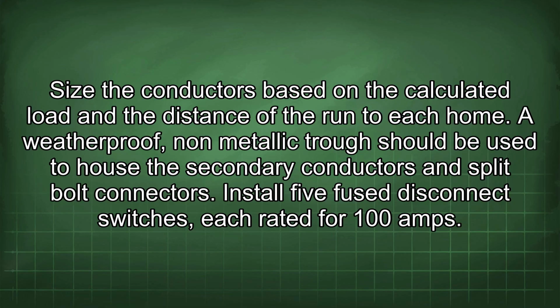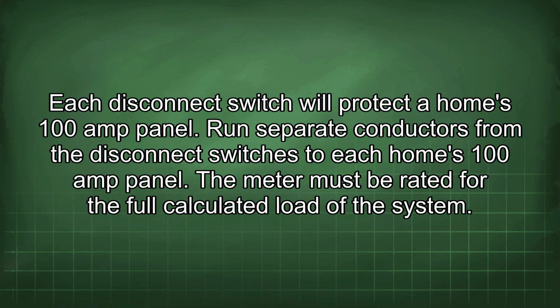Install 5 fuse disconnect switches, each rated for 100 amps. Each disconnect switch will protect a home's 100 amp panel. Run separate conductors from the disconnect switches to each home's 100 amp panel. The meter must be rated for the full calculated load of the system.